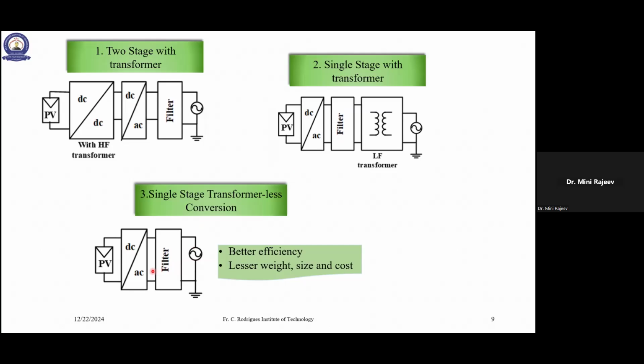But what is the problem with this? One problem is you cannot step up the voltage at the grid side. So it will be better if the inverter has a boost capability. Boost capability in the sense, step up capability. And another advantage is because the transformer is eliminated, it will have better efficiency, lesser weight, size, and cost. So these are the advantages of transformerless power conversion.